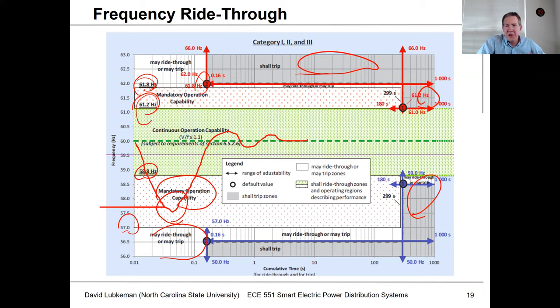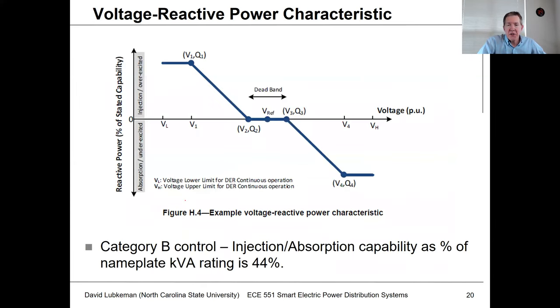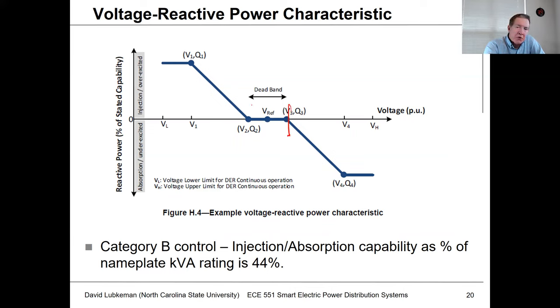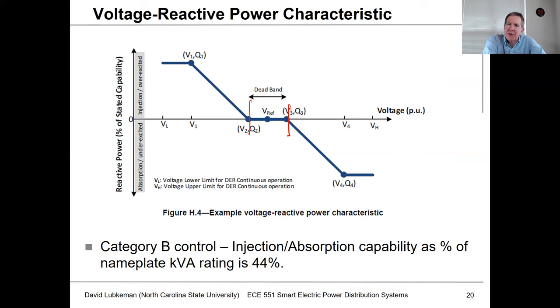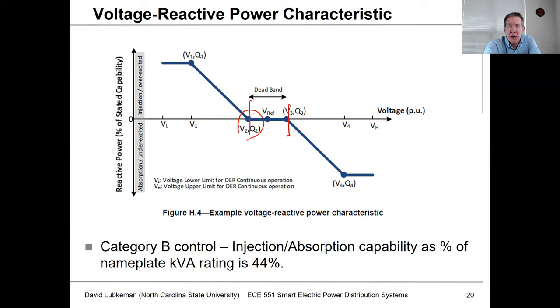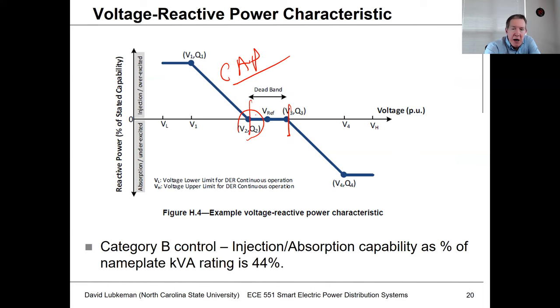You've got some flexibility of adjusting these set points within the unit — they're actually all programmable as far as these cutoffs. Another thing you see in the 2018 compliant devices is a voltage-reactive power characteristic. You have voltage on the x-axis, and if you go up too high in voltage or too low in voltage, then you're going to have a reactive power injection or absorption. Remember, we talked about capacitors — putting a capacitor in there boosts voltage. So if you have a unit that injects VARs, that's going to boost the voltage. The voltage gets below a dead band set point, and you basically have this thing act like a variable capacitor, injecting reactive power up to some type of limit.